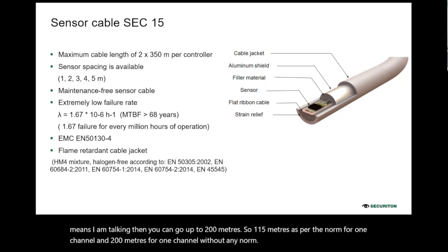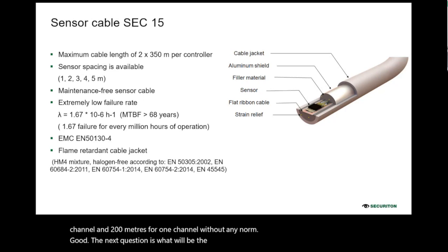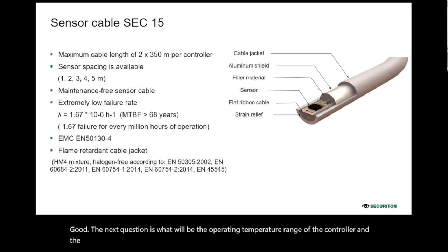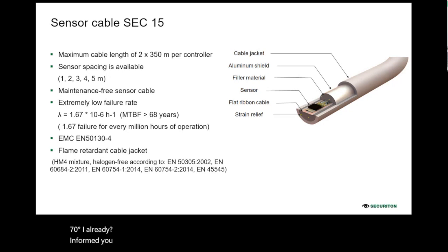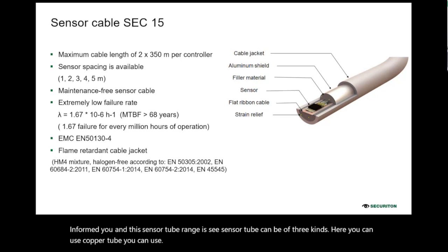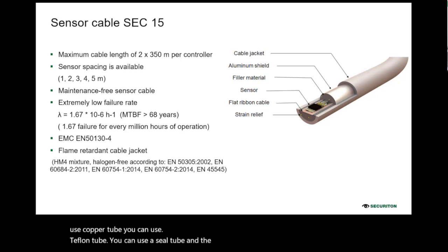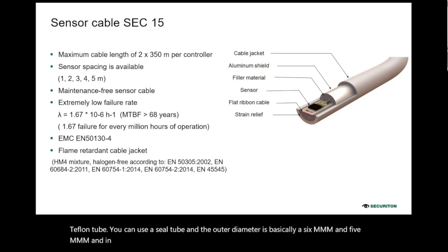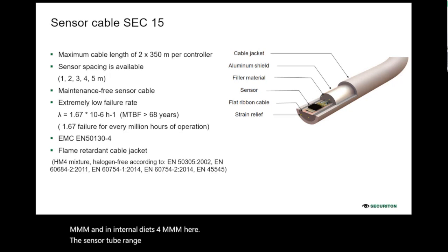Good. The next question is, what will be the operating temperature range of the controller and the tubes? The controller is -30 to +70 degrees, as I already informed you. And the sensor tube can be of three kinds. You can use a copper tube, a Teflon tube, or a steel tube, and the outer diameter is 6 mm or 5 mm, and the internal diameter is 4 mm. The sensor tube range is somewhere around -40 to +185 degrees.